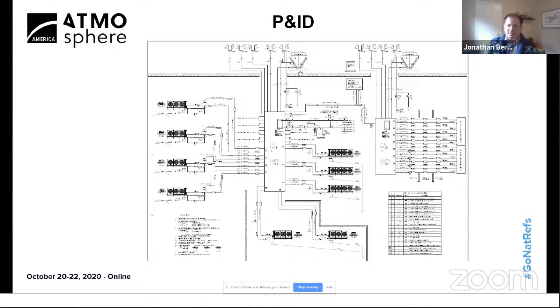Each of these racks had a dedicated cascade cooler, and both racks were served by a backup emergency generator and a backup condensing unit, such that if there was a power failure at the plant, these two devices would kick on and maintain pressure on the racks so that we didn't have any release of CO2 due to overpressurization.